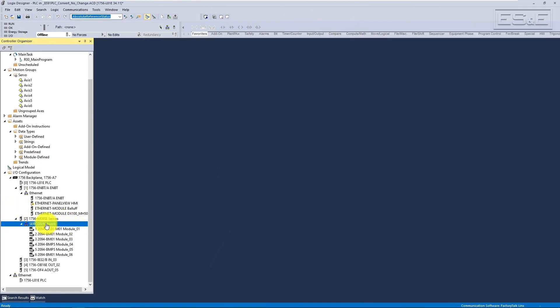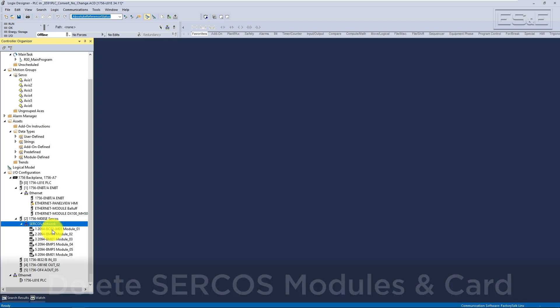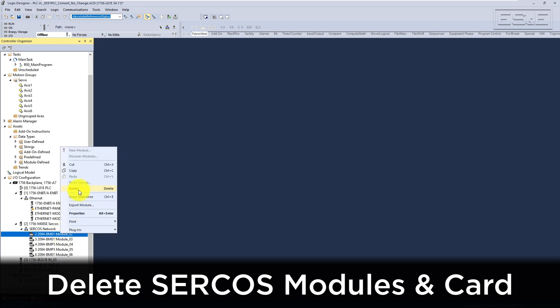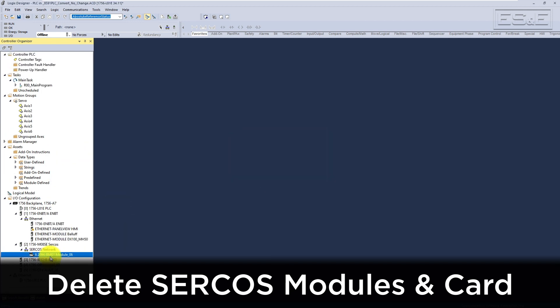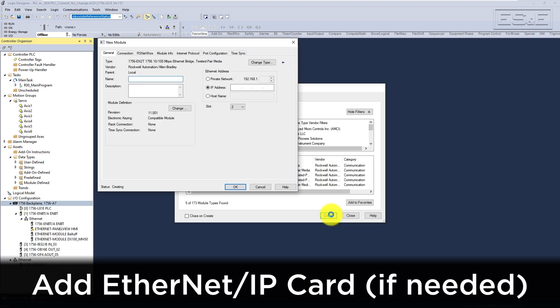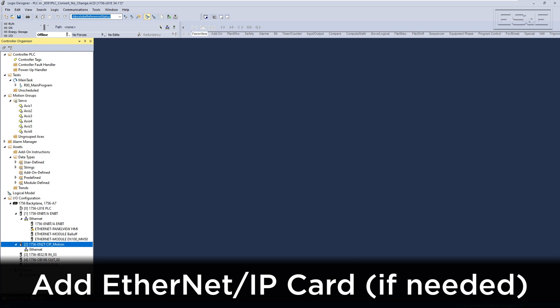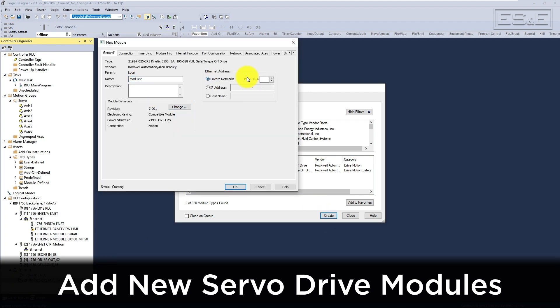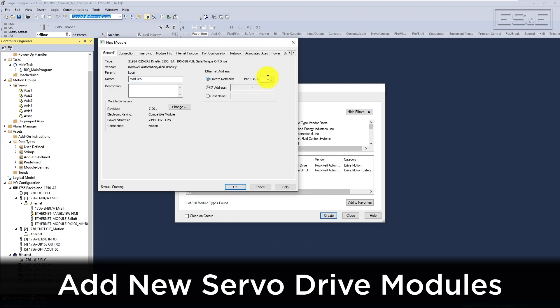Once all the tags have been corrected, the next step is to convert the communications configuration in the controller organizer. Since we will no longer be using the SERCOS communications card, we can delete all the SERCOS modules and the SERCOS card from the IO configuration tree. If you're using an Ethernet IP card, you can add that to the PLC IO configuration. If you're using a PLC with onboard Ethernet, then you can just add the new servo drive modules directly to the controller's Ethernet IP configuration. Now you can associate the new Ethernet IP modules to the CIP axes we created earlier, and also take the time to configure the power settings in the module properties.